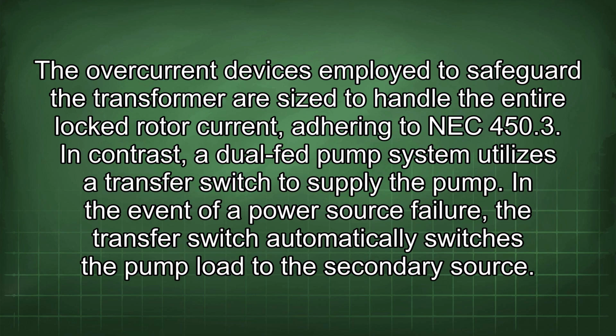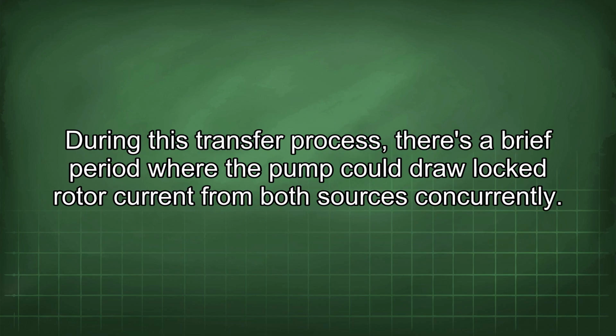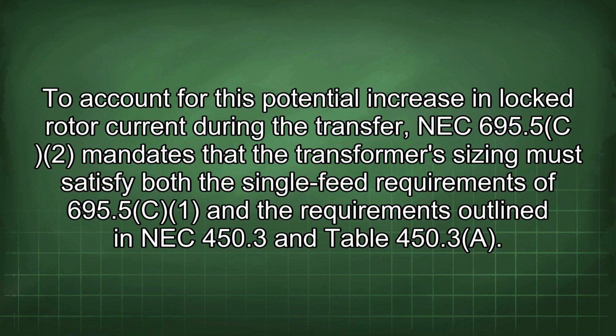In contrast, a dual-fed pump system utilizes a transfer switch to supply the pump. In the event of a power source failure, the transfer switch automatically switches the pump load to the secondary source. During this transfer process, there's a brief period where the pump could draw locked rotor current from both sources concurrently. To account for this potential increase in locked rotor current during the transfer, NEC 695.5 C2 mandates that the transformer's sizing must satisfy both the single-feed requirements of 695.5 C1 and the requirements outlined in NEC 450.3 and Table 450.3(A).